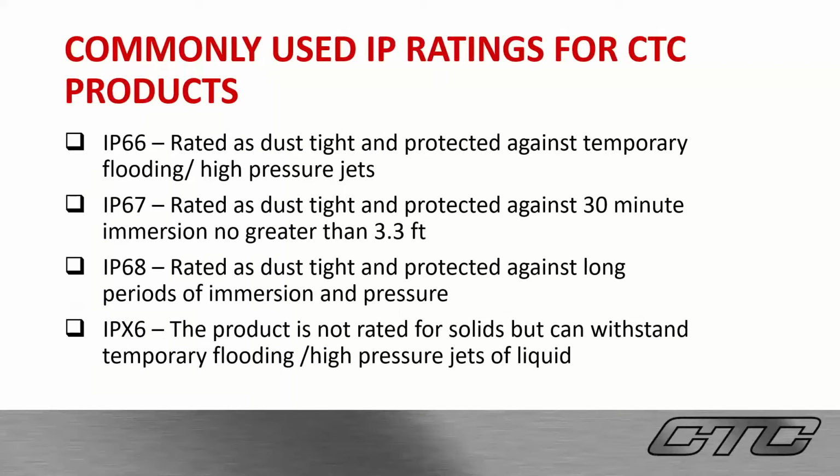So, commonly used IP ratings for CTC products. We have IP66, which is rated as dust tight and protected against temporary flooding and high pressure jets. We have IP67, which is rated as dust tight and protected against 30-minute immersion with no greater than 3.3 feet. And then we have IP68, which is rated dust tight and protected against long periods of immersion and pressure. And then below that, we have the IPX6 rating, which is for products that are not rated for solids, but can withstand temporary flooding and high pressure jets of liquid.